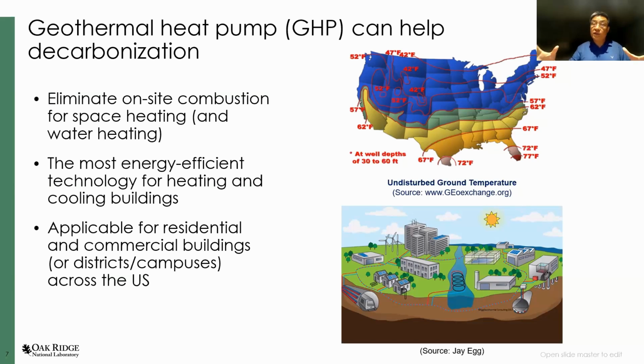Because this system utilizes a common water loop to connect the heat pump and the ground heat exchanger, this water loop can also be expanded to include many other resources, such as groundwater, wastewater, or a nearby river or lake. Those resources can all be utilized by the heat pumps as a heat sink or heat source, so that they can run at high efficiency.